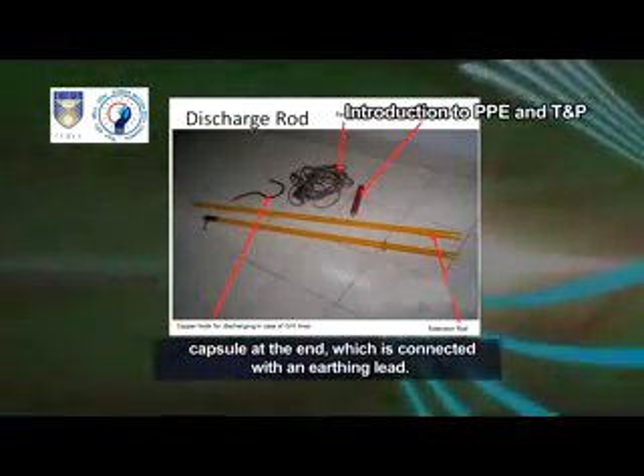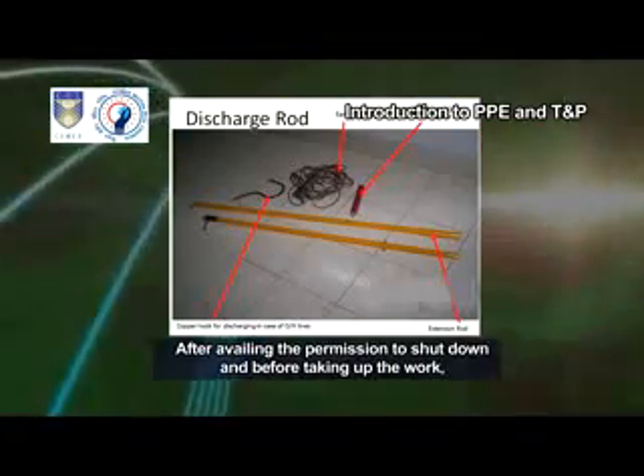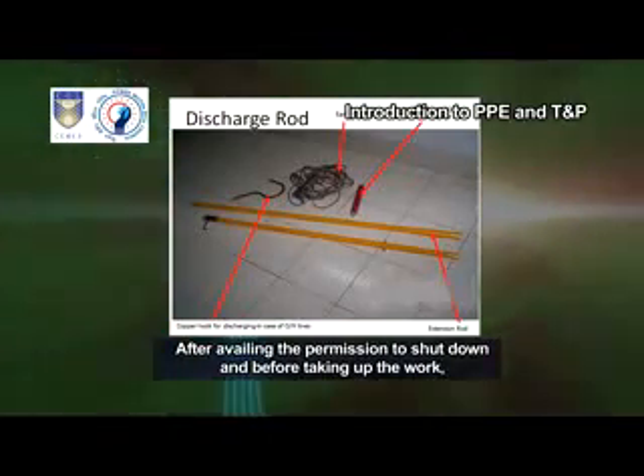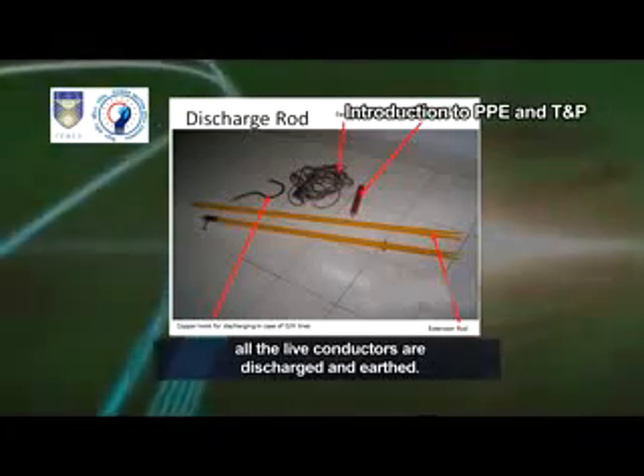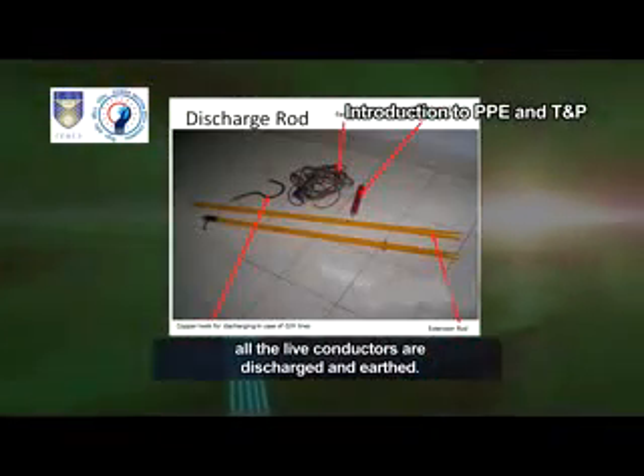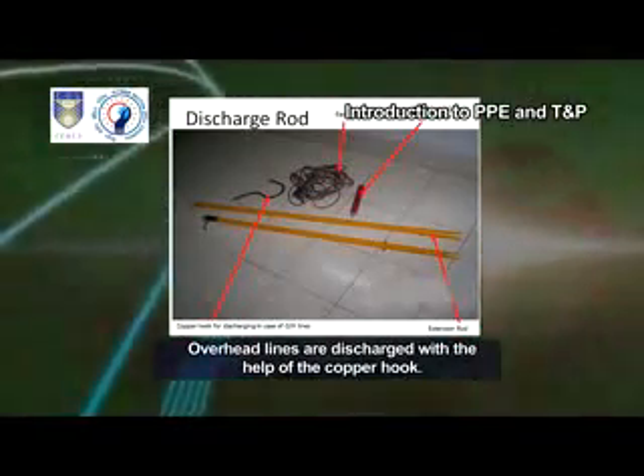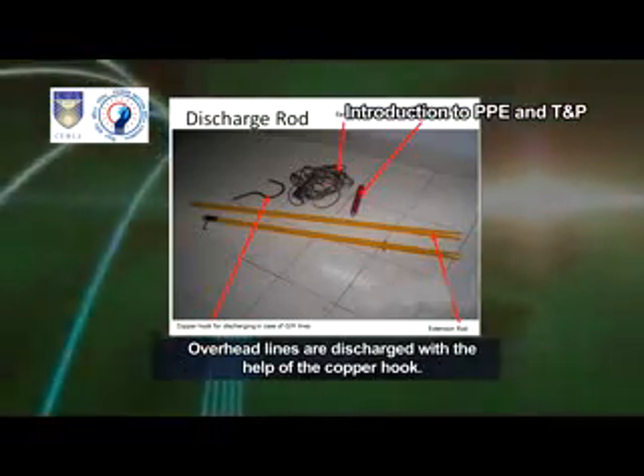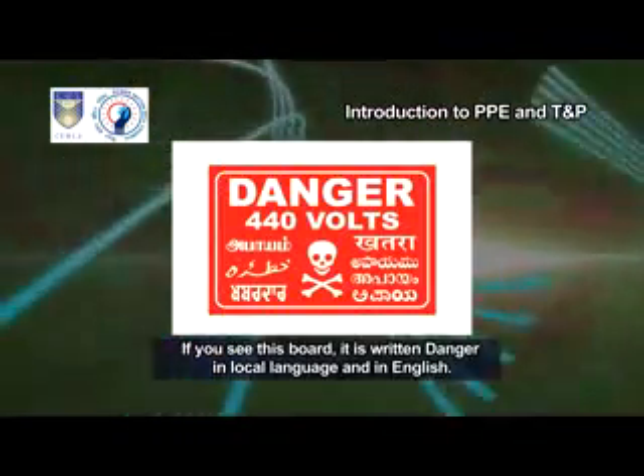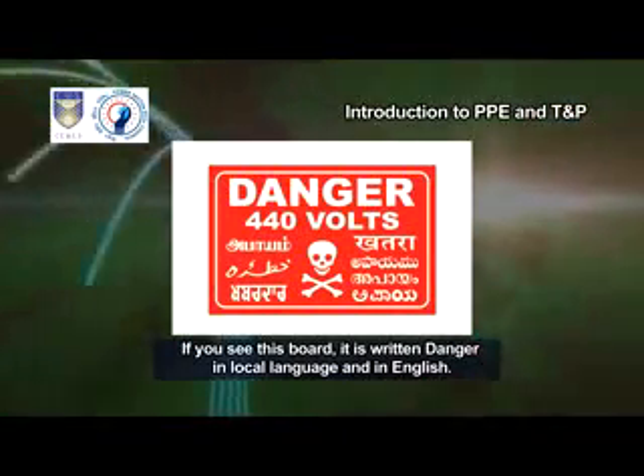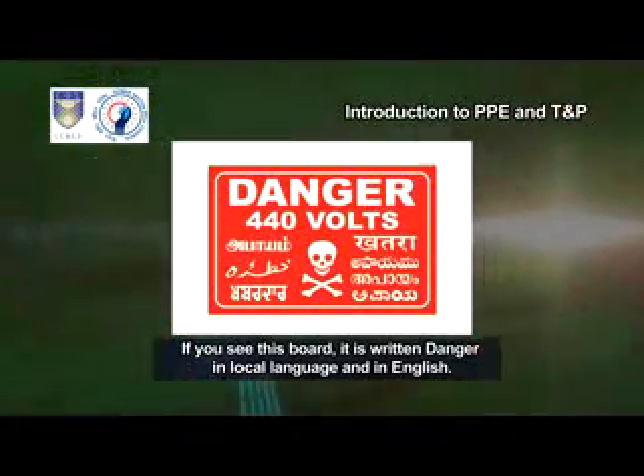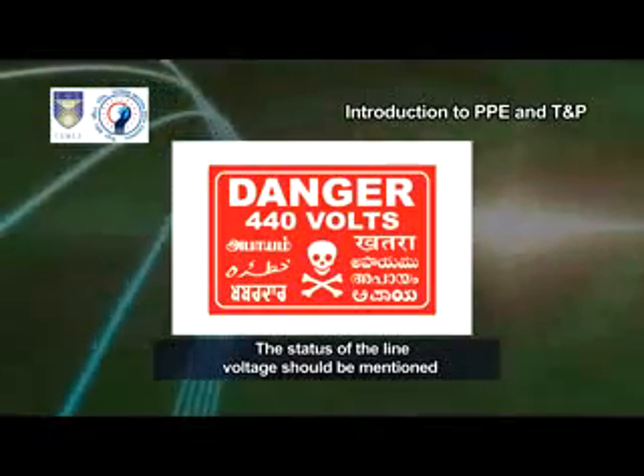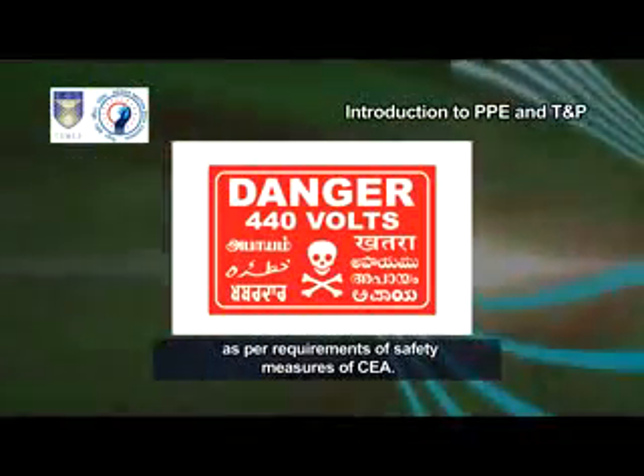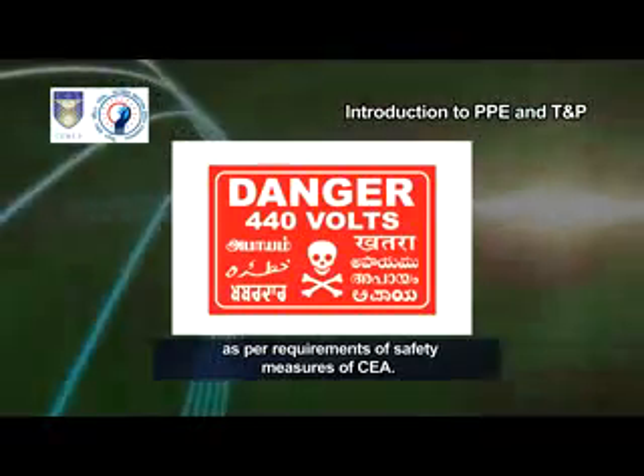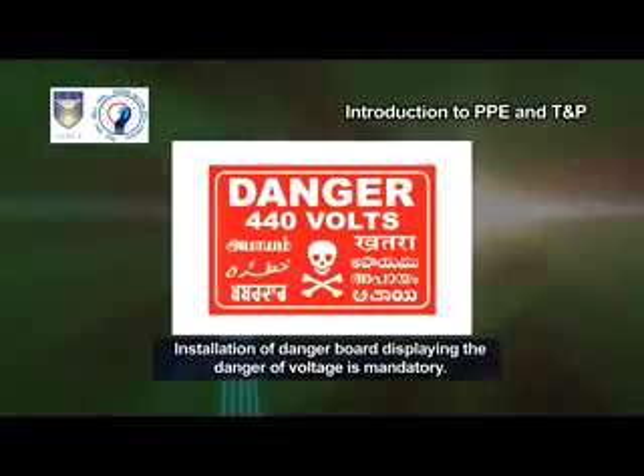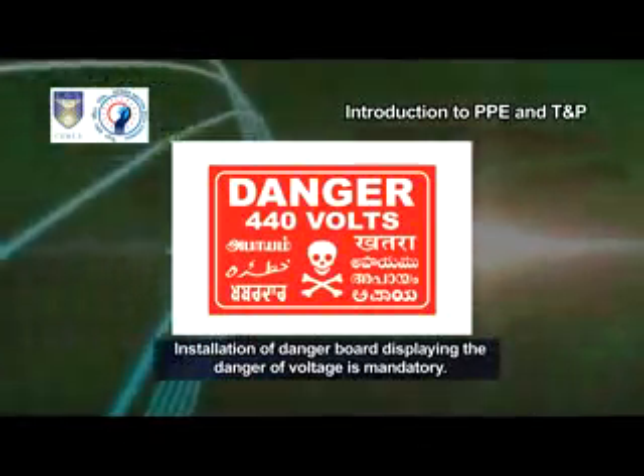which is connected with an earthing lead. After availing the permission to shut down and before taking up the work, all the live conductors are discharged and earthed. Overhead lines are discharged with the help of the copper hook. If you see this board, it is written danger in local language and in English. The status of the line voltage should be mentioned as per requirements of safety measures of CEA. Installation of a danger board displaying the danger of voltage is mandatory.